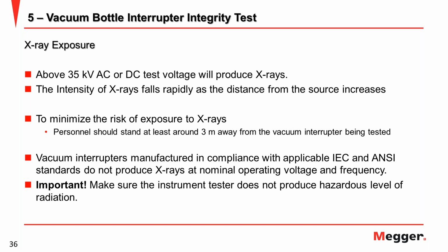And vacuum interrupter manufacturers, in compliance with applicable IEC and ANSI standards, do not produce X-ray at nominal operating voltage. So as long as they operate at the nominal operating voltage, all vacuum interrupter manufacturers comply with this standard and do not produce X-ray effect. But for testing vacuum, normally we need to inject higher voltage, maybe 2 times plus 1 kV. So this is why to be careful to choose the equipment tester. And our product has been proved and tested on the OEM breaker, which proves our equipment does not produce this X-ray when we do testing.